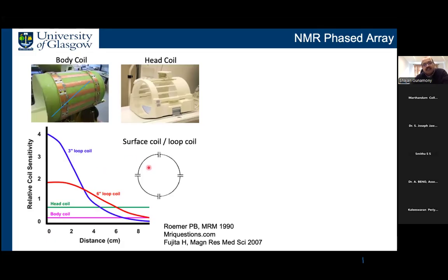If you now use a small surface coil closer to the anatomy, then it will have a much stronger sensitivity, but the penetration would be poor because it's a small coil, and it drops off quickly as you go away from the coil. So the NMR phased array technique basically takes the high sensitivity of a small coil, and that sensitivity is then spread across a larger volume. This way you generate an image with a much higher signal to noise ratio. So this is basically the essence of the NMR phased array.